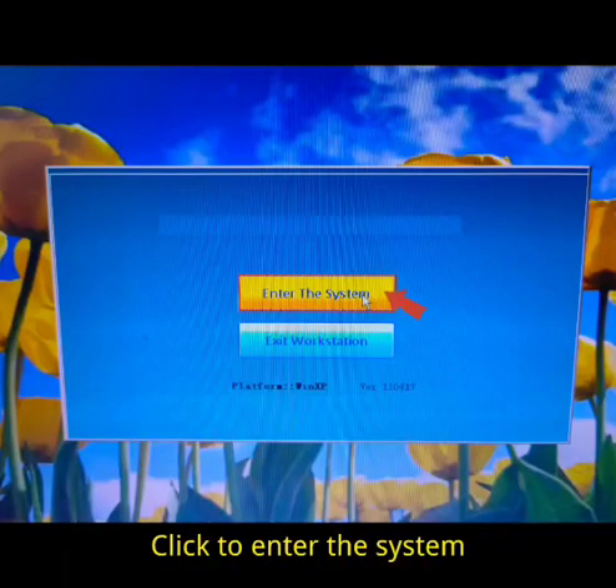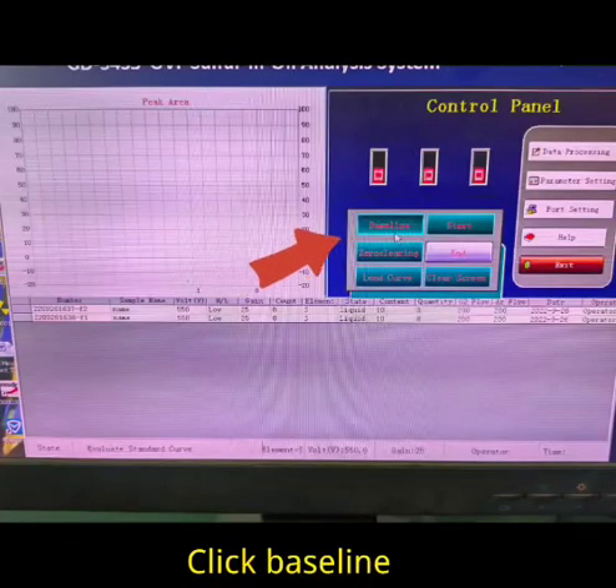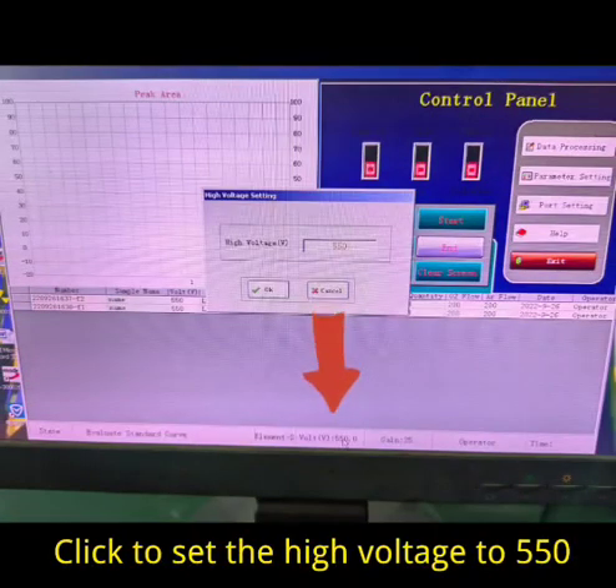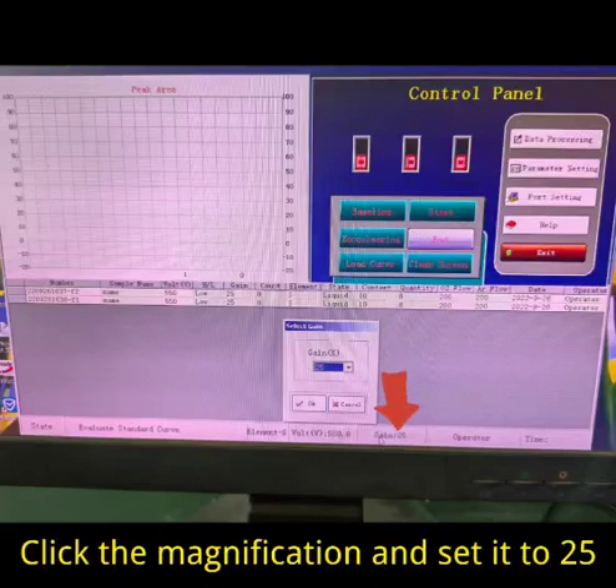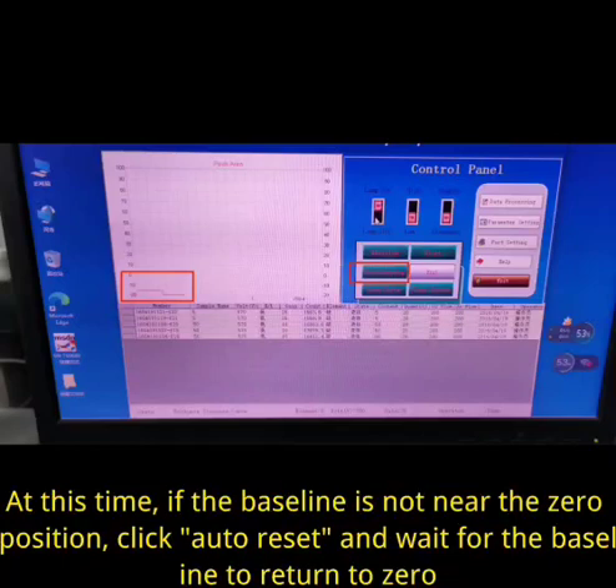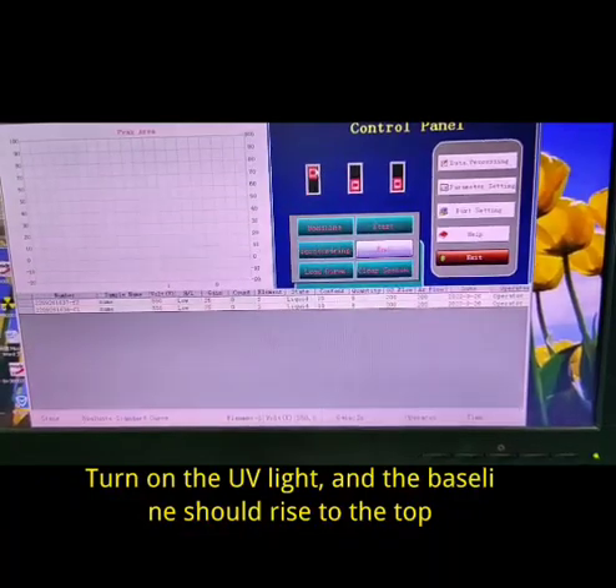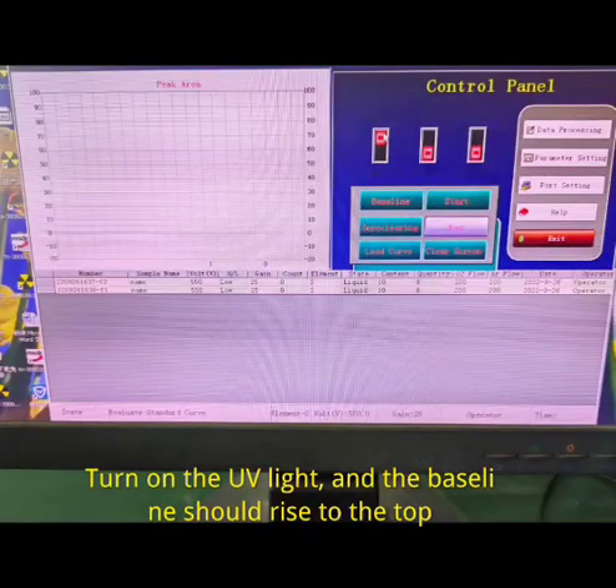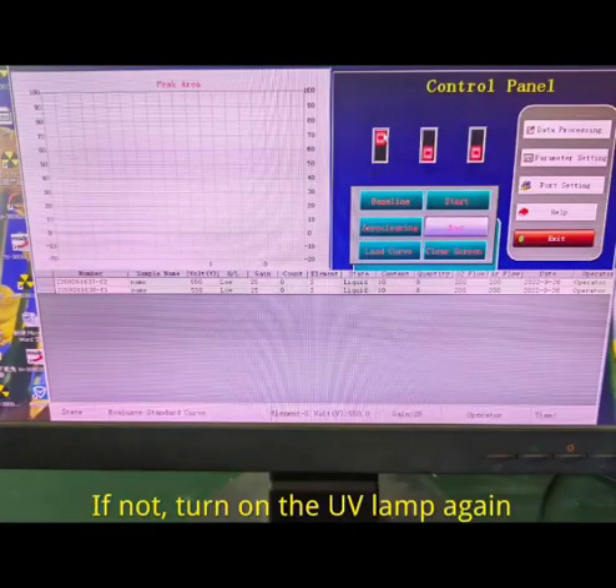Click to enter the system. Click baseline. Click to set the high voltage to 550. Click the magnification and set it to 25. At this time, if the baseline is not near the zero position, click Auto Reset and wait for the baseline to return to zero. Turn on the UV light, and the baseline should rise to the top. If not, turn on the UV lamp again.